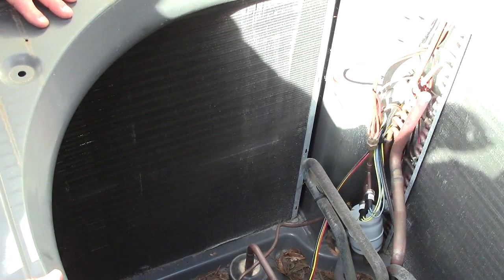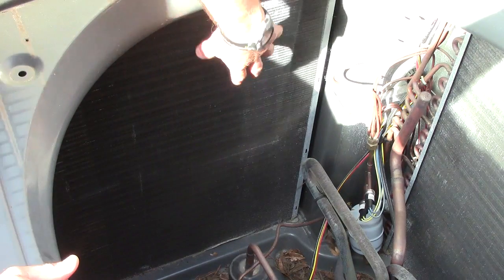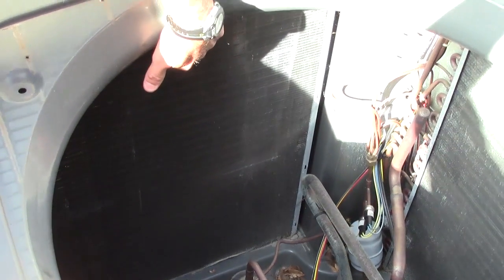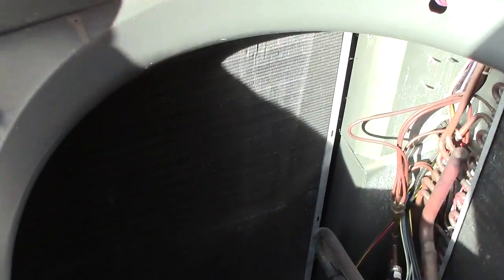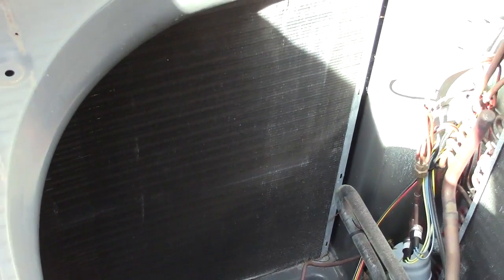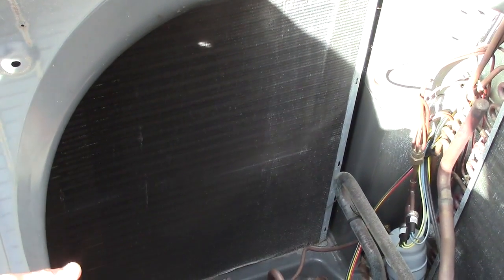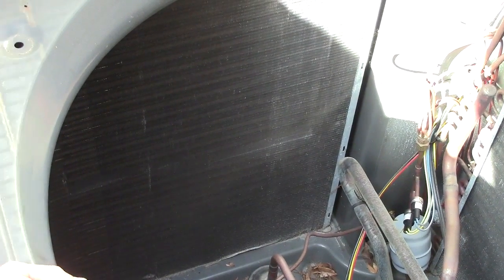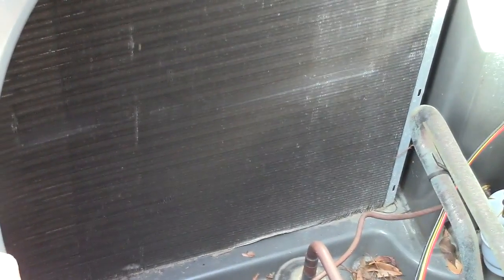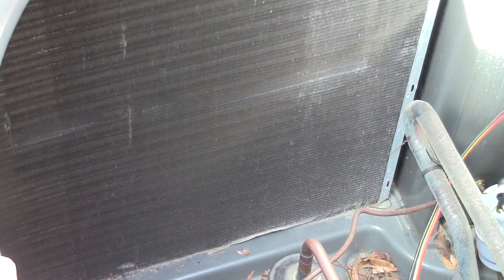Inside this machine, we're in the middle of a checkup, and this is the coil surface here. What we're looking for here is damaged fins and oxidation. The aluminum in Florida, we have such a high salt content that these coils can actually become damaged from the environment and from debris and baseballs and children bumping up against it. So it's very important to look at these surfaces, make sure that they're clean. The cleaner they are, the more efficient this machine's going to work and provide cold air for you.